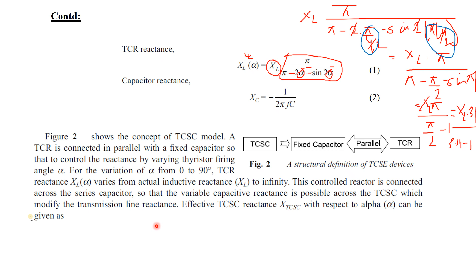So the effective TCSC reactance with respect to alpha can be given as this equation. Okay, so this is the modified equation, the effective equation, because the TCSC reactance has to be calculated, whereas this is the TCR reactance. Across the reactor there is a capacitor connected, so that the control reactor is connected across the series capacitor so that the variable capacitive reactance across TCSC is modified, which modifies the transmission reactance.